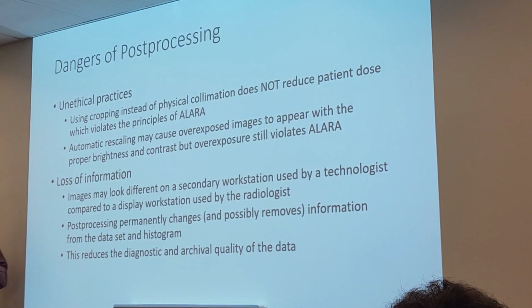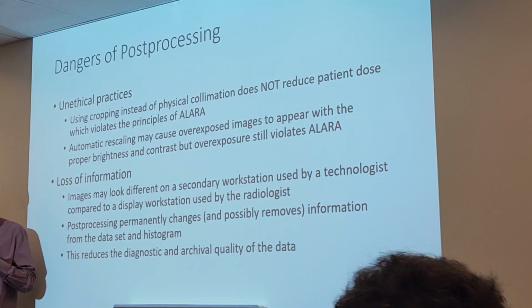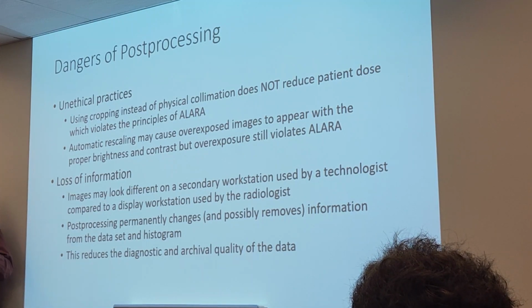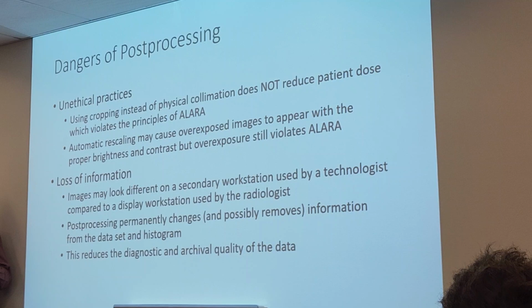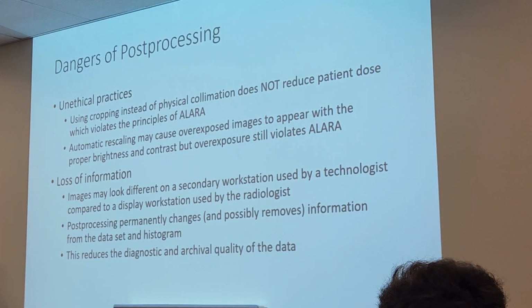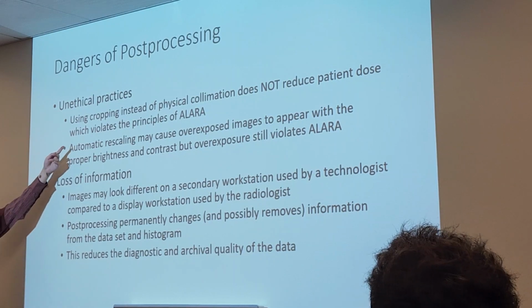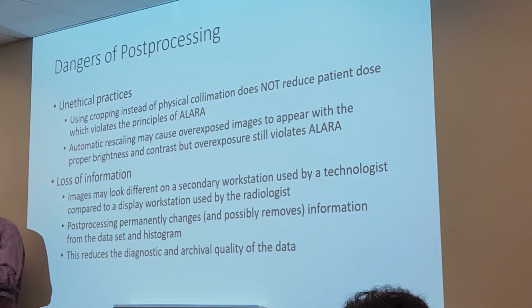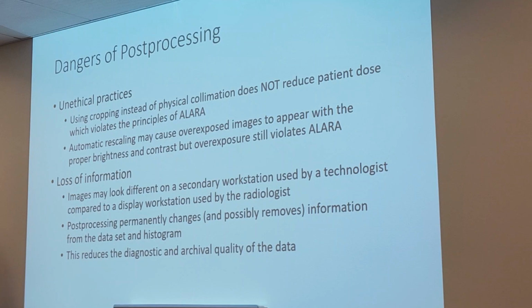The amount of dose is actually going higher and higher because when you are underexposed, it's obviously underexposed, you can see the quantum mottle. When it's overexposed, well, you don't see anything bad. It looks good. Why? Because of automatic rescaling. Automatic rescaling makes your image look pretty good no matter what.